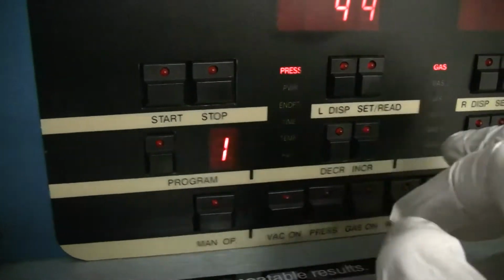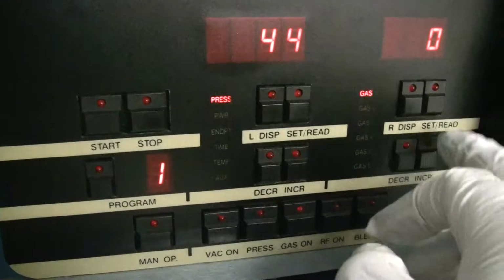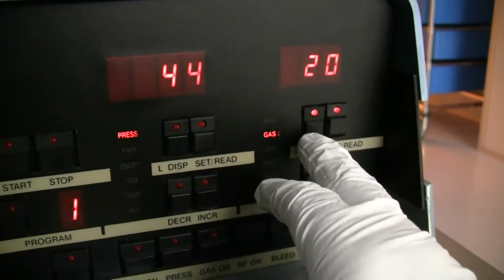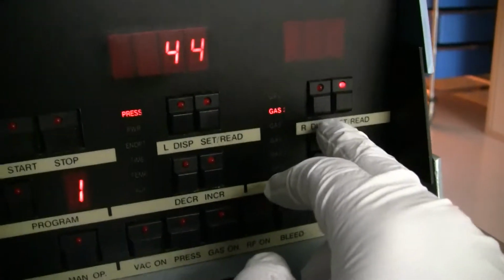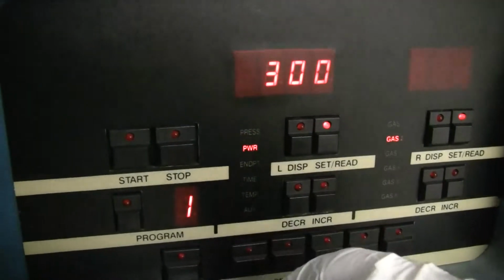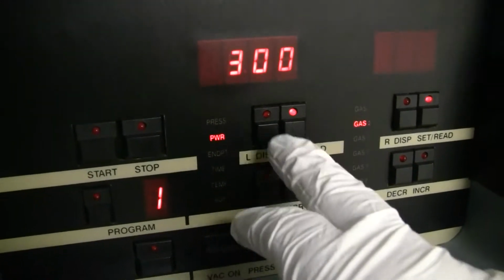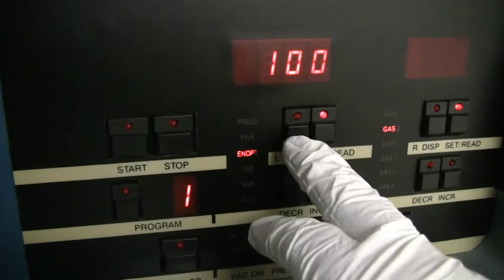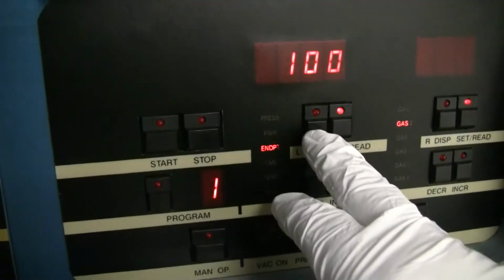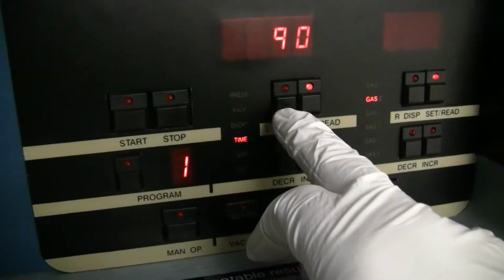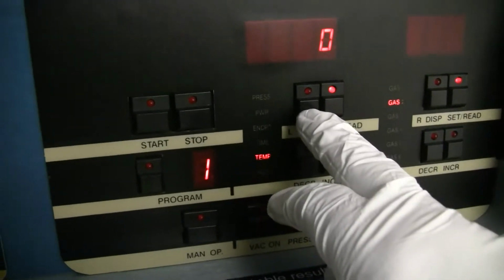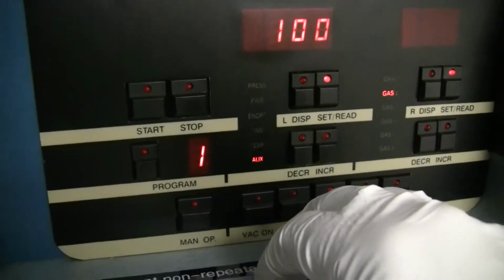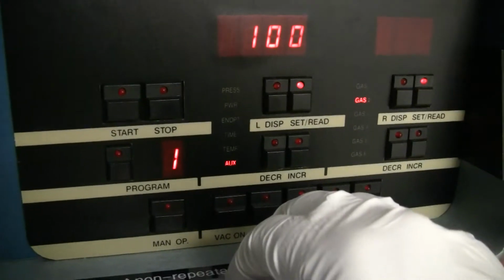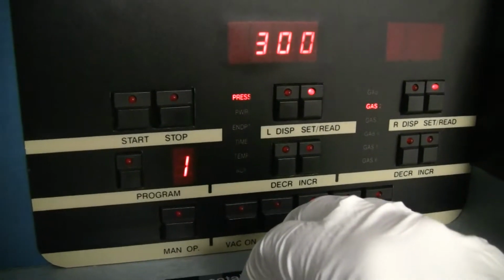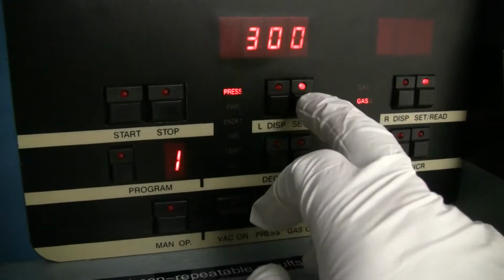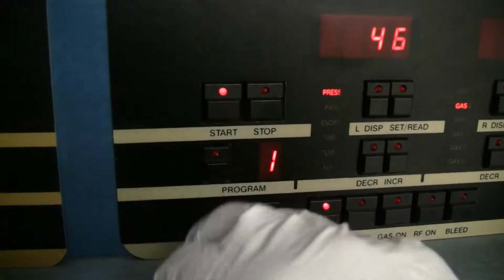Anyway, all right, so let's check out the parameters on program 1. So, 0 gas 1, 20 gas 2. This is basically what I was just running. Power set to 300. Endpoint 100, that's for an endpoint detector that we don't actually have. Process time 90 seconds. Temperature not used. Auxiliary is the base pressure that it's got to get to before it starts the program. And the set point pressure is 300 millitorr. All right, so I think we can go ahead and start it.